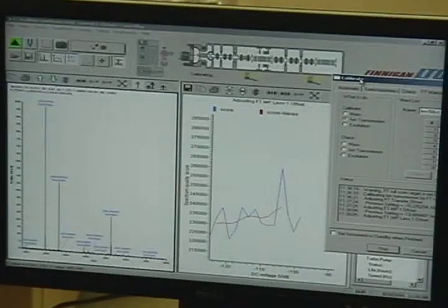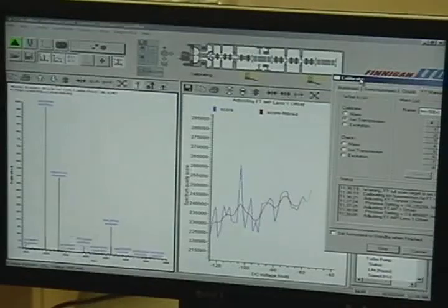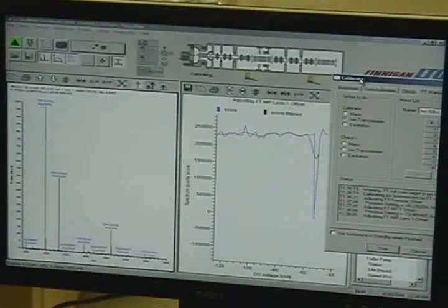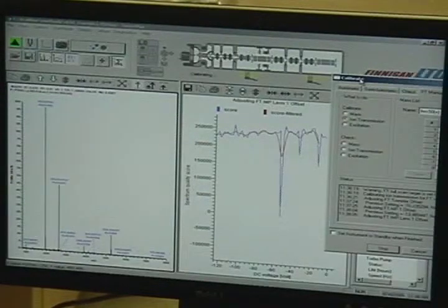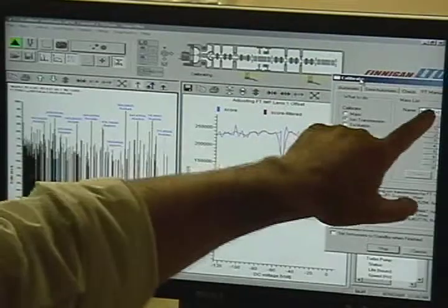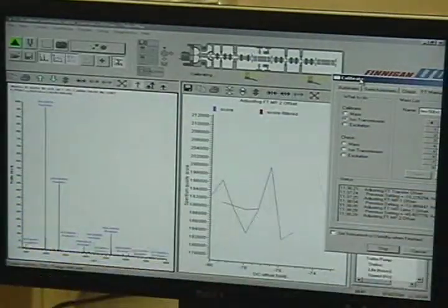Okay. And remind me what causes that. That's the transmission optics. Say it was off, say the Ultramark was real high. What you could do is get rid of the masses out of the Ultramark list right here for your transmission calibration. You don't have to do it for mass, just transmission.